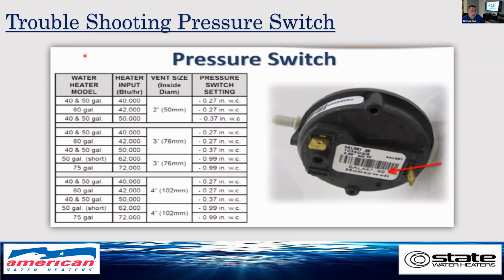Make sure which switch you have before testing. In this chart, you can see there are 3 typical switches that we use: a negative 0.27, a negative 0.37, and a negative 0.99. The BTU input value is usually what indicates which switch we use. So usually on our 42 and below will be the negative 0.27. Our 50,000 BTUs was usually a negative 0.37. And when we get up to our 72,000, 62,000, we're at a 0.99.